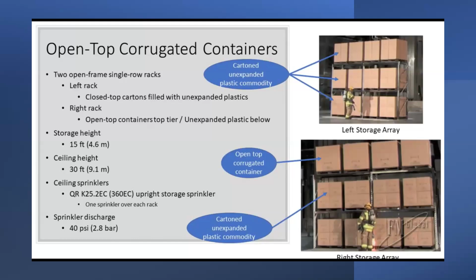It is well known that plastic storage can produce severe storage fires. You might be wondering if open-top corrugated containers present the same challenge to a ceiling sprinkler system's ability to control a fire. In this demonstration fire, 2 rack arrays are set up side by side. Each array is under a single quick response sprinkler. The storage height is 15 feet or 4.6 meters, and the ceiling height is 30 feet or 9.1 meters. The left storage array consists of the FM Global standard carton unexpanded plastic commodity with no open-top containers. The right storage array is identical, except the top tier of storage is replaced with an open-top corrugated container. The single sprinkler over each array will deliver a flow of 159 gallons per minute or 600 liters per minute, which is more than adequate for cartoned unexpanded plastic storage at this storage height.